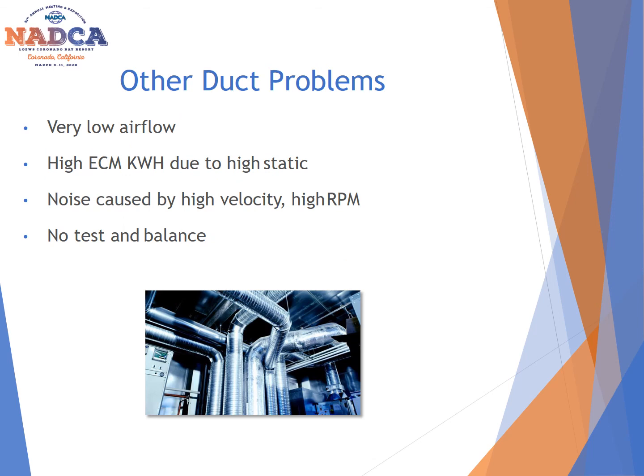Some of the other issues you can run into associated with duct problems is very low airflow, because things are maybe disconnected or blocked, potentially, for a variety of different reasons. Noise caused by high velocity or from the blower running at high RPMs, and the system was never tested or balanced properly whenever it was installed.